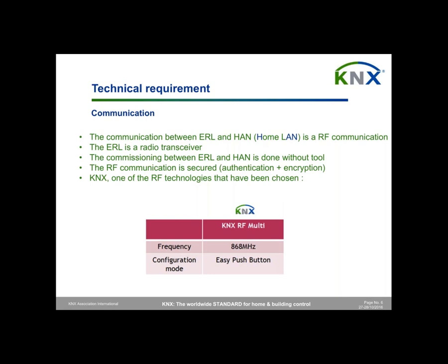The RF communication must be secured, authentication and encryption. And for this, KNX has been chosen to be one solution for this. So today, if you want to develop such a module, you have to use KNX RF with easy push button configuration to fit all the technical requirements we have seen in this page.